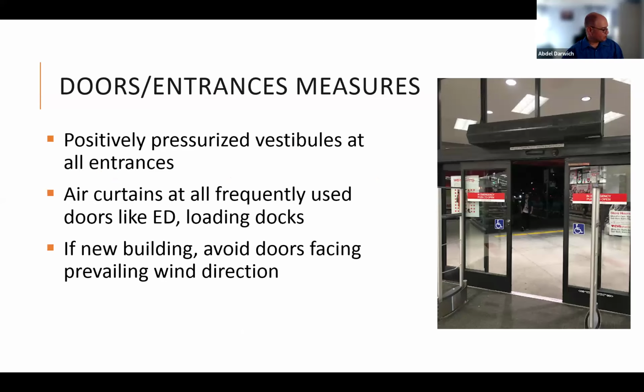The second way for wildfire smoke to enter is through doors and entrances. Usually we recommend having positively pressurized vestibules at all entrances, so there is no direct communication between the hospital and the outside. If you cannot do that, you can add air curtains at frequently used doors like the ED, the emergency department, and the loading docks. Those air curtains bring air in, so it's like a curtain of air. Basically, when the door opens, wildfire smoke cannot get in. If it's a new building and you have an architect who's open to working with you, you can design the building to avoid the main door facing the prevailing wind direction, so the main door is always downwind.